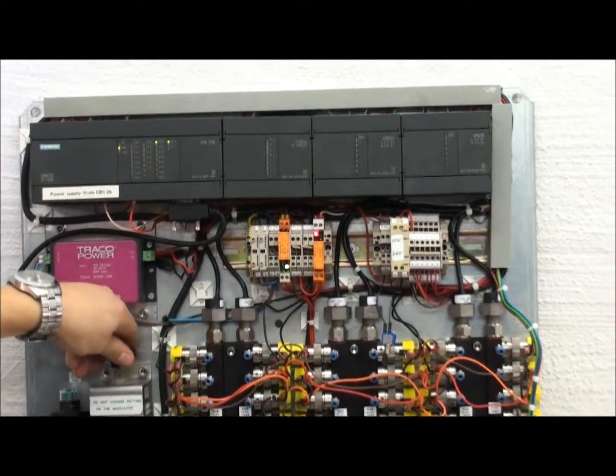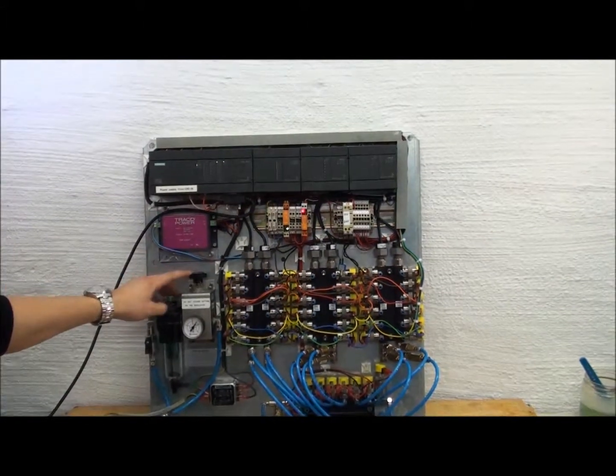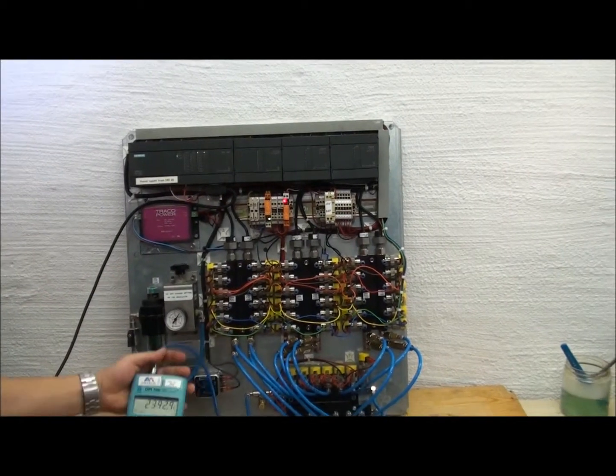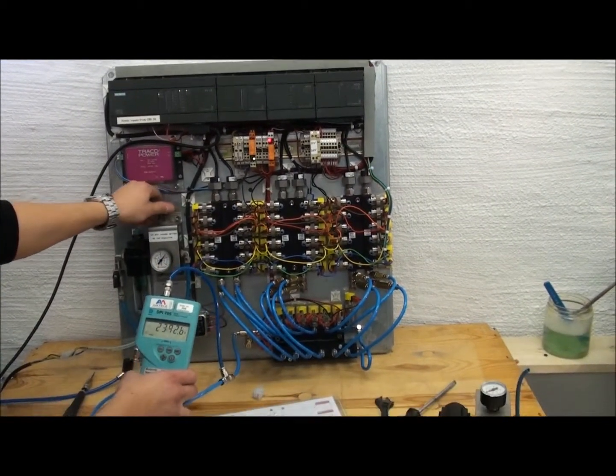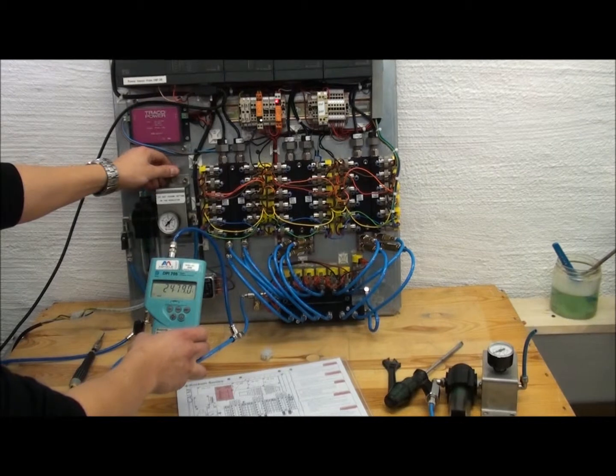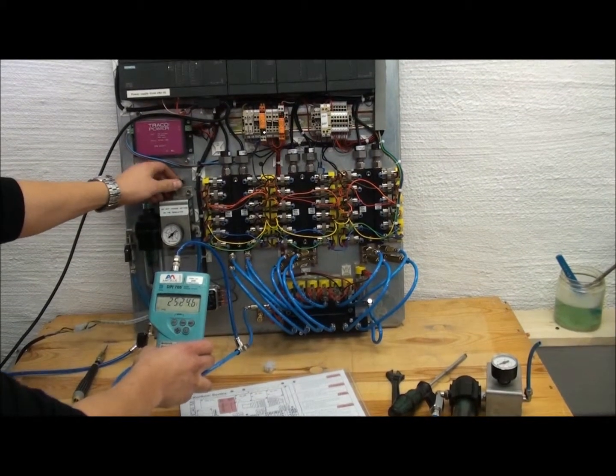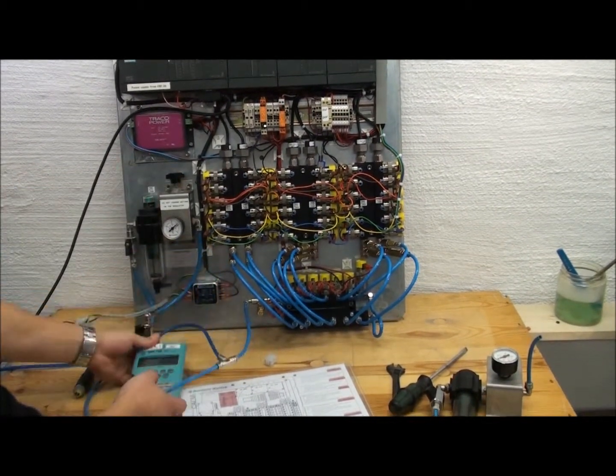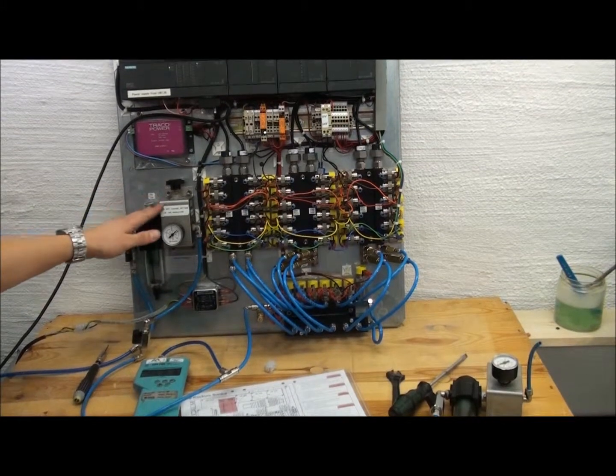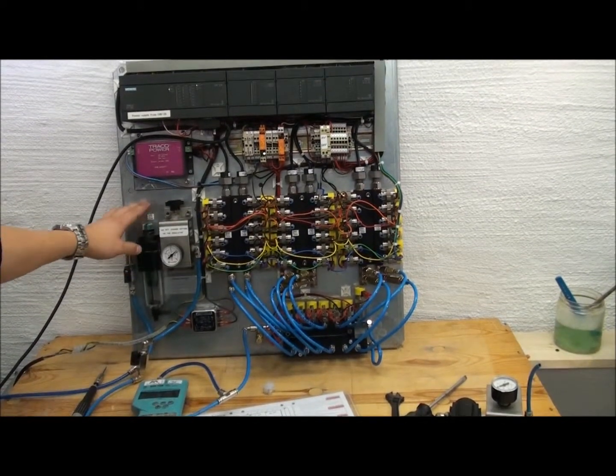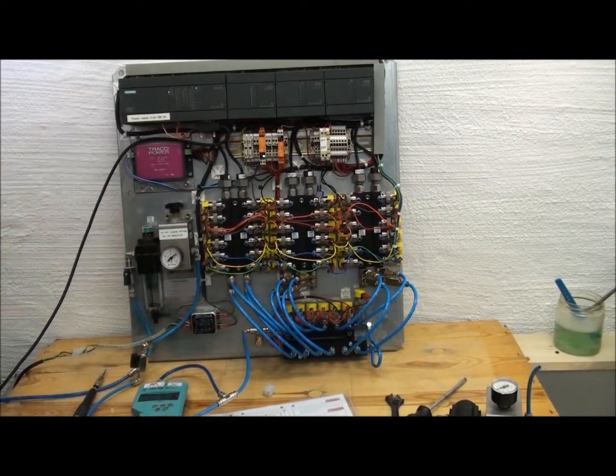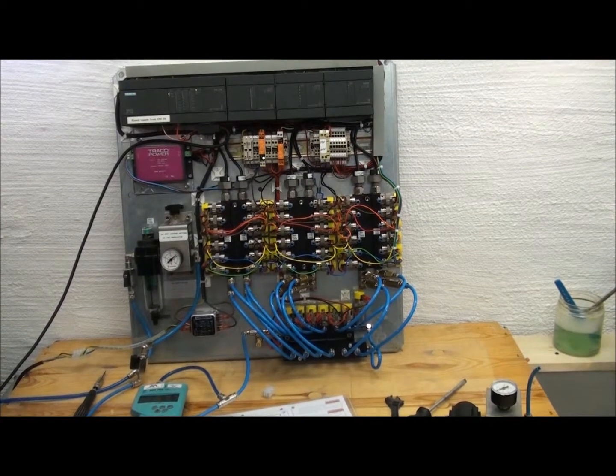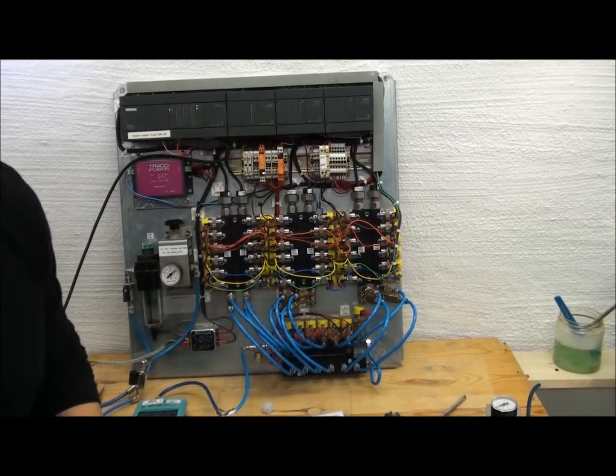Now we can just go up with the pressure, because we're not calibrating anymore. We're running the system with a little bit less than 3 bar. So we just go a little bit above the calibration pressure. And now the system should be up and running and already calibrated.